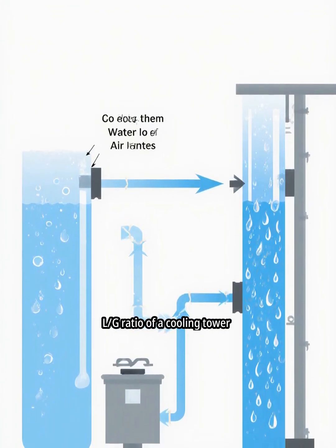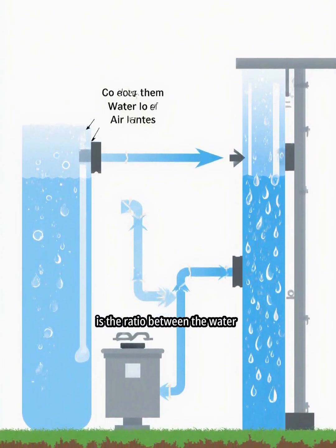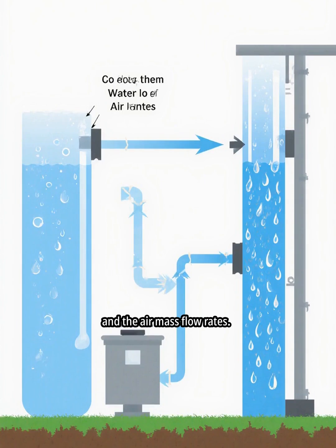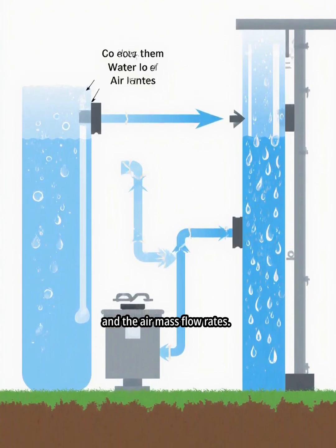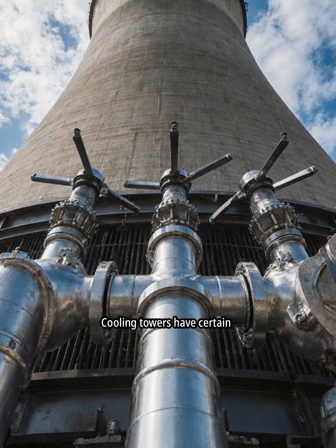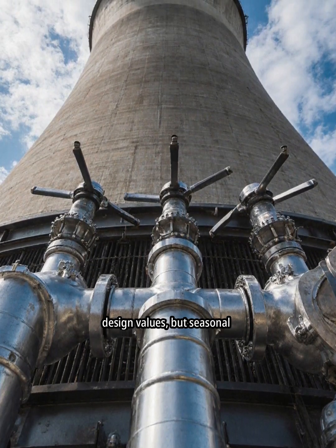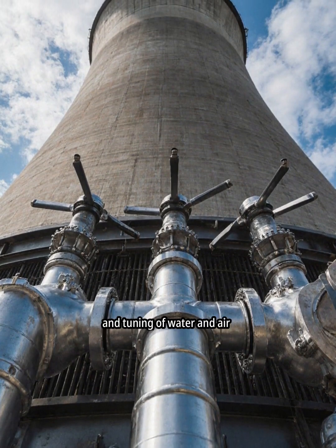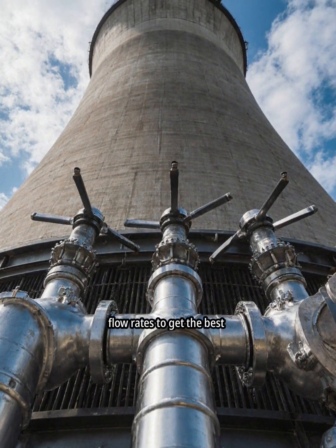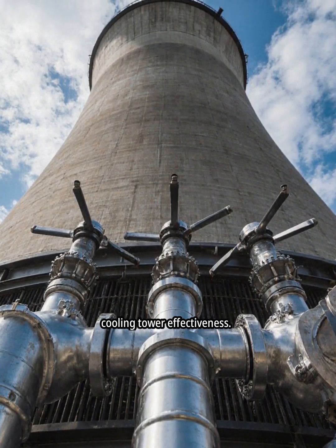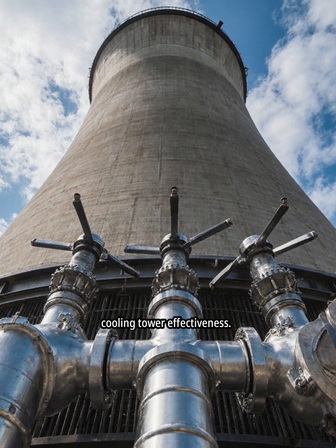Liquid gas ratio. L divided by G. The L divided by G ratio of a cooling tower is the ratio between the water and the air mass flow rates. Cooling towers have certain design values, but seasonal variations require adjustment and tuning of water and airflow rates to get the best cooling tower effectiveness.